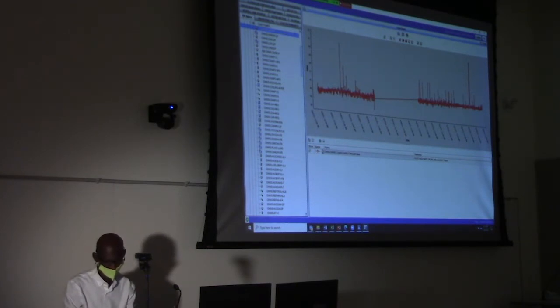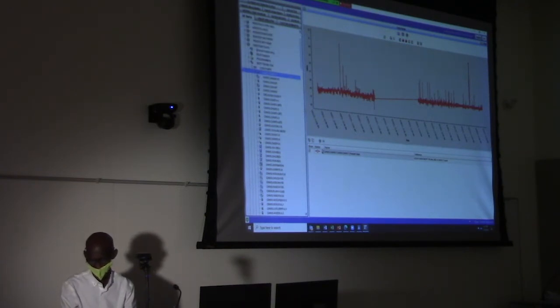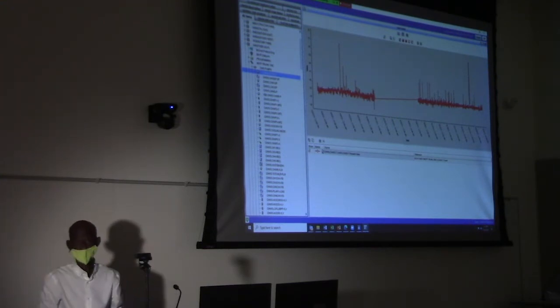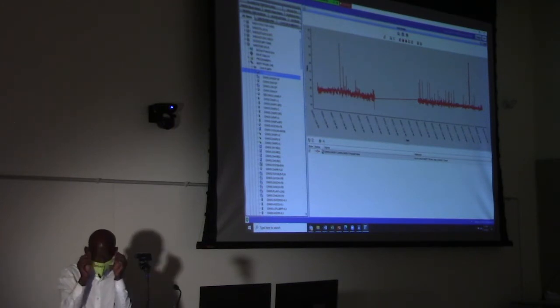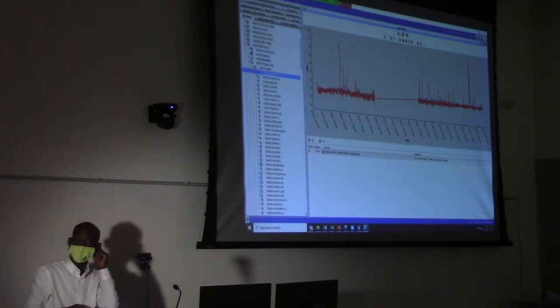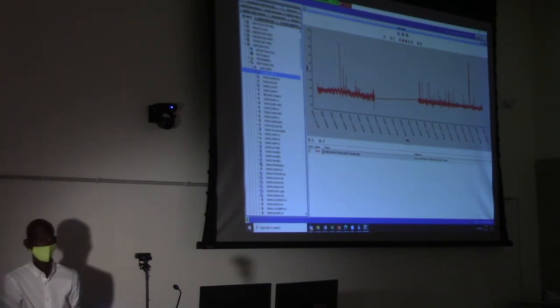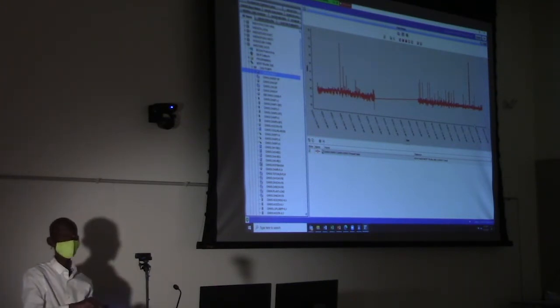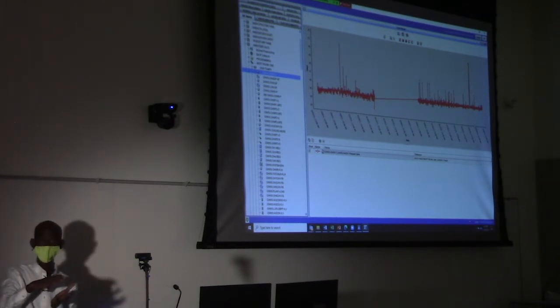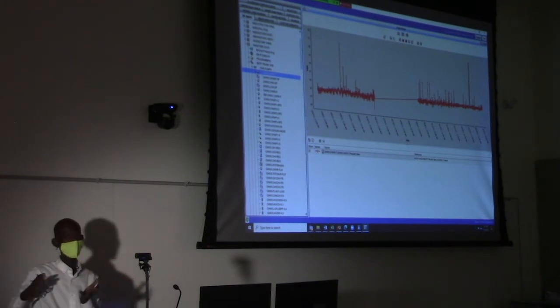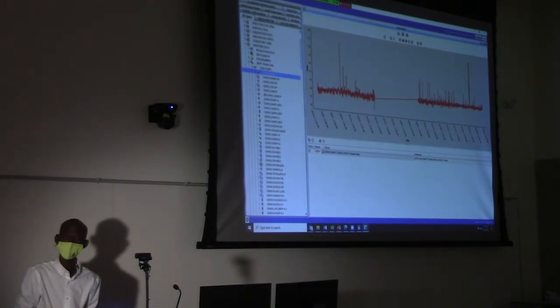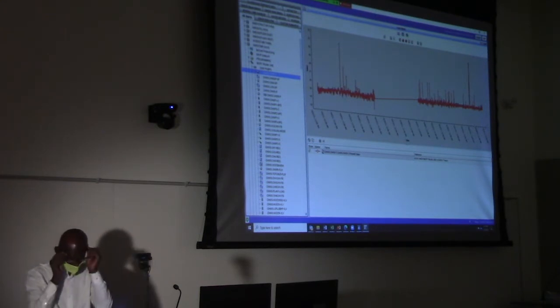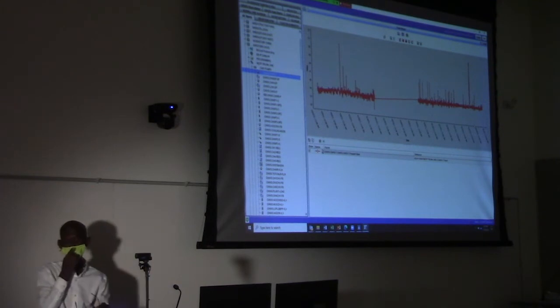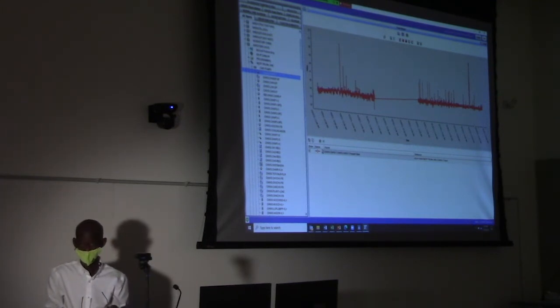So what would the spikes in water temperature indicate? It can be due to many issues. Sometimes it may be a power failure, or the chillers are not running properly, or you may have pumping issues, because when you have a pumping issue, for instance, instead of delivering a larger flow, you deliver a lower flow. If you have a lower flow, the water you're providing is not heating up properly. So those are a few things. Or it may not be a problem if the outside air temperature was reasonable.